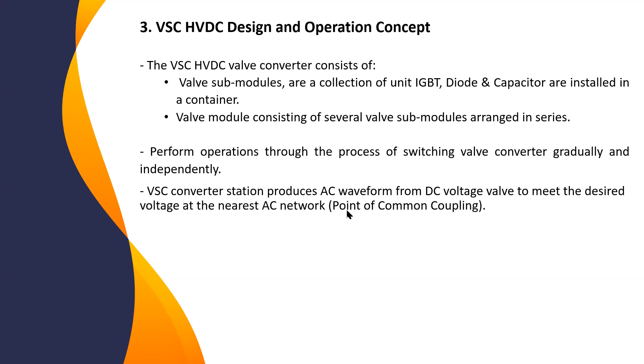In terms of waveform here, the VSC converter station produces an AC waveform as well, because we have to maintain the AC voltage close to the AC network. We call it the point of common coupling. So today we have three generations of VSC. The first generation was energized commercially in 1999, using a 2-level converter. And then the second generation, we call it a 3-level converter. The third generation, modular multi-level converter.